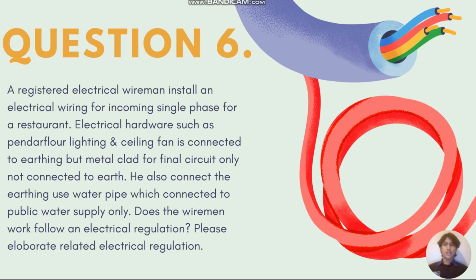First of all, as you can see, the question is: a registered electrical wireman installs electrical wiring for an incoming single phase for a restaurant. Electrical hardware such as pendarflour lighting and ceiling fan is connected to earthing, but the metal clad for the final circuit only is not connected to earth. He also connects the earthing using a water pipe which is connected to the public water supply only. Does the wireman's work follow the electrical regulation?